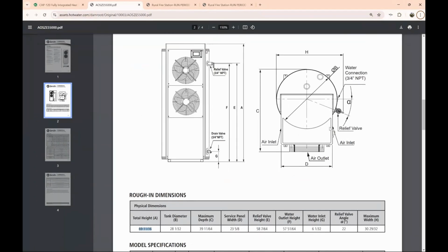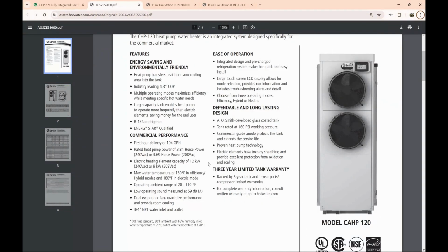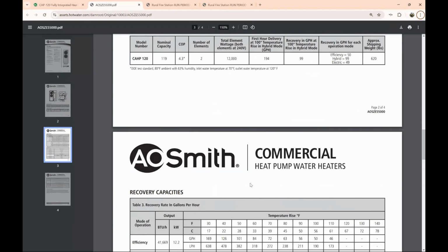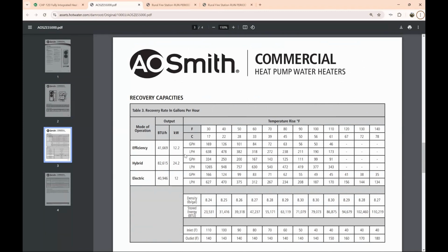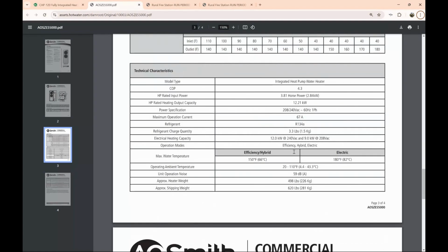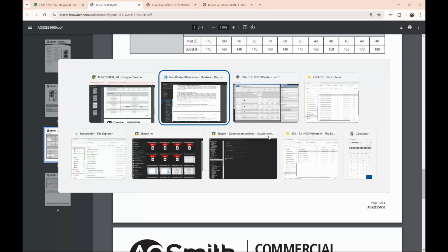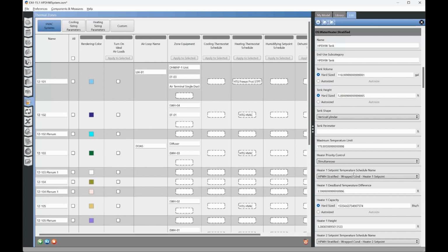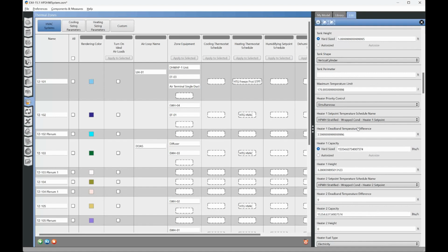So going back to our hot water heater, it looks like our maximum element capacity is 12 kilowatts. So it looks like they're probably able to operate at the same time. So that's fine. Let's just set them as operating at the same time, simultaneous. Next one is heater 1 set point temperature. This is going to be the temperature these supplemental heaters are going to try to maintain in the tank.